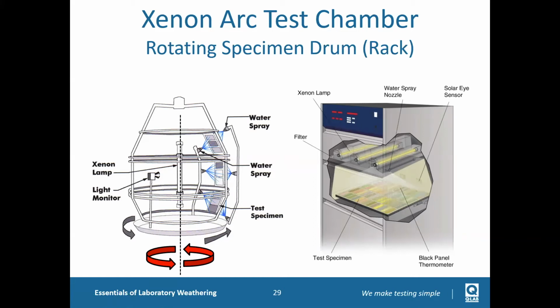So many customers may ask, I think the rotating drum has better uniformity. That is actually another topic, but I would like to tell you that we have done lots of research. If you are interested in that research, you can visit our website or send an email to me. I'll forward the research paper to you. That is because by structure, we have a flat array, but we have 3 lamps, and we have a reflective chamber wall. So the specimen here or here receives not only the direct sunlight from the lamp, but also the light reflected from the chamber wall. This is the first point. The second point is we have 3 light monitors. And when we do calibration, we calibrate 3 spots, which means left, middle, right, and they all have the same irradiance reading.